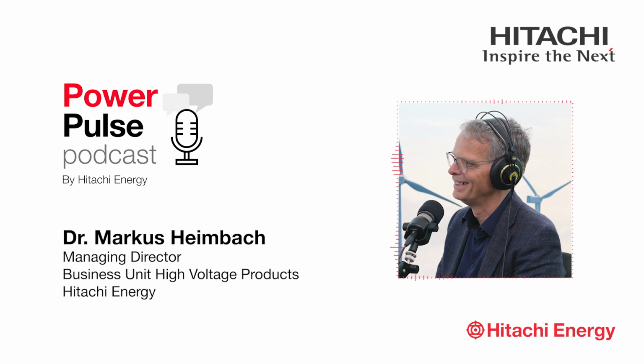Yes. And that's why our industry has the obligation to get rid of SF6. We are now working to replace the SF6. We call it EconiQ, an SF6-free gas mixture, to be more precise, which has the same reliability you need, much better environmental behavior, and the complete scalability from maybe 10 kV up to 400 kV or 1000 kV that SF6 had.